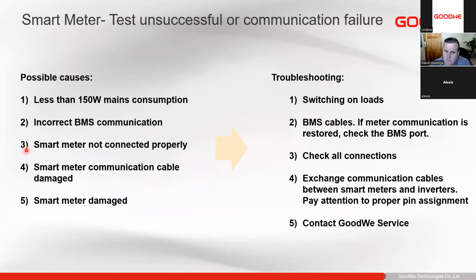So lastly, if we aren't detecting the smart meter, so if you see on PV Master it's saying communication failed to the smart meter, it could be that cable because the cable's already fixed to the inverter. Sometimes routing it or running it does cause an issue. Sometimes customers will extend that cable. If you extend it, I always recommend it, replace the entire cable. Do not use the RJ45 connector male to female to connect them to an external cable. That always causes problems. It's an extra point for interference.